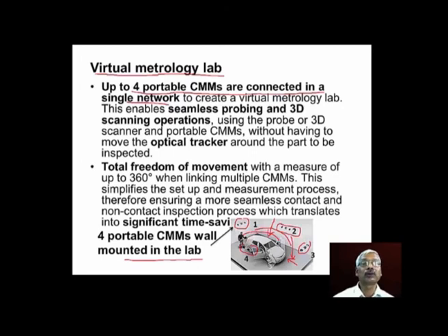That is, up to 4 portable CMMs are connected in a single network to create a virtual metrology lab. This enables seamless probing and 3D scanning operations using the probe or 3D scanner and portable CMMs without having to move the optical tracker, that is a dual camera system, around the part to be inspected. If we use only one optical tracker or dual camera system, we will have to move around the workpiece. So that is avoided by networking 4 trackers in the system.